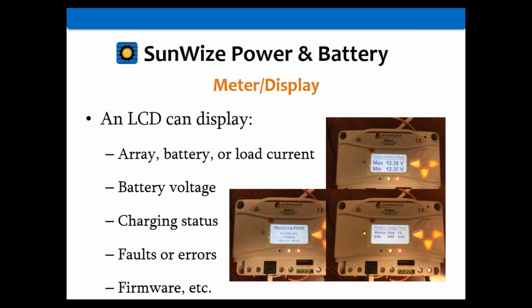Some units also have a high voltage disconnect to protect the load from high voltages. We had a problem with this last winter during extreme cold in the Northeast, where the HVD started kicking in. One easy way to diagnose it was to scroll through the display to the error messages, which showed the high voltage alarm was engaged. Using the display, you could then adjust settings to prevent it—disabling the high voltage alarm, raising the disconnect threshold, adjusting temperature compensation, or setting a max battery voltage.